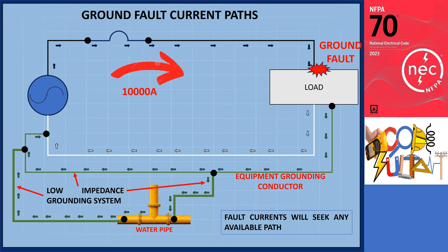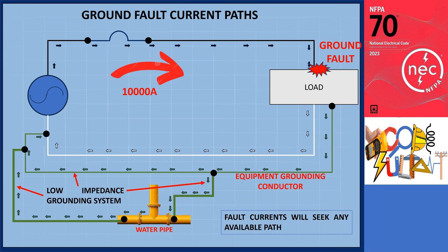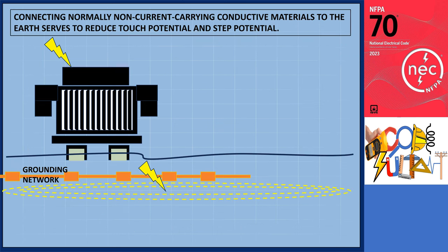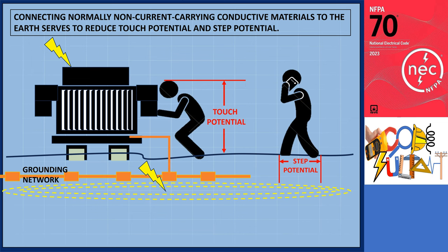It is a common misconception that current takes the path of least resistance and that grounding will prevent someone from experiencing electrical shock. In reality, to prevent electrical shocks, we need to focus on reducing touch potential or step potential by ensuring that all elements are at the same or equal potential.